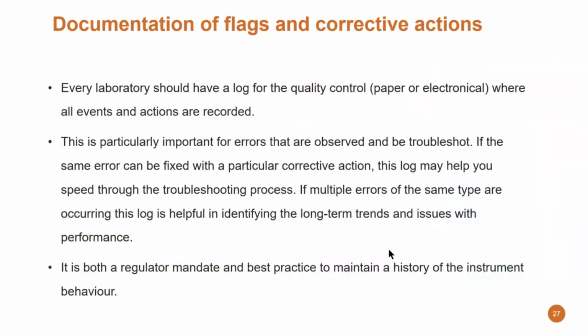Documentation of flags and corrective actions. Every laboratory should have a logbook, electronic file, or whatever, for the quality control results, where all events and actions are recorded. This is particularly important for those errors that are observed and troubleshooted. If the same error can be fixed with a particular corrective action, this log may help you later on to speed through the troubleshooting process. If multiple errors of the same type are occurring, this log is also helpful to identify long-term trends and issues with the performance. It is both a regulatory mandate and also best practice to maintain a history of the instrument behavior.